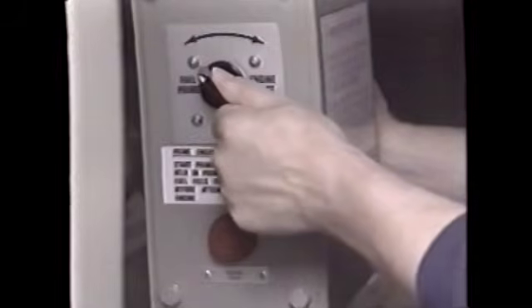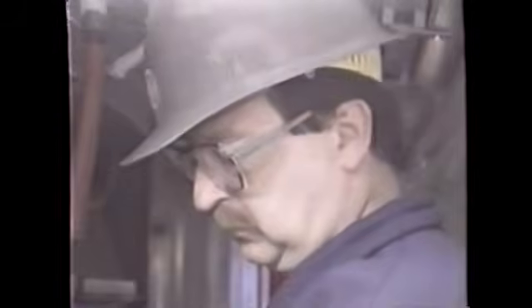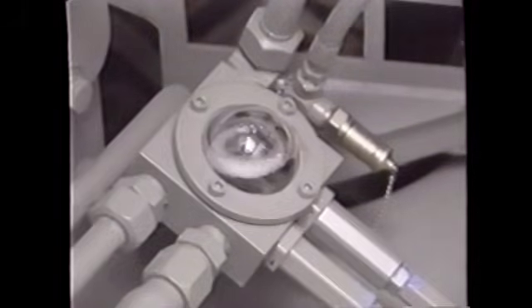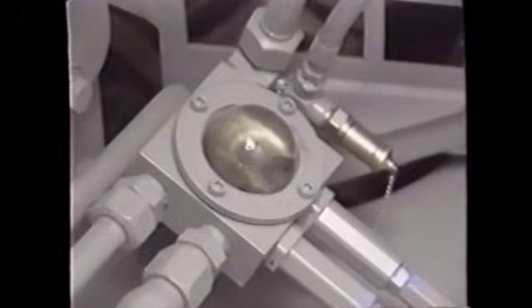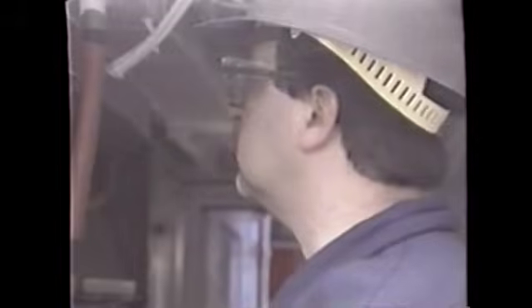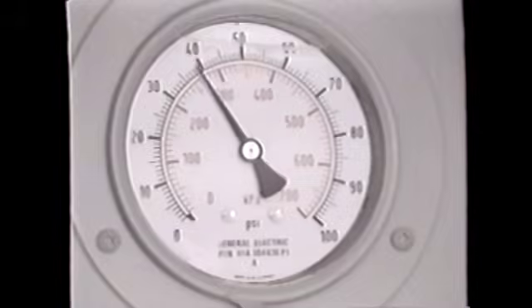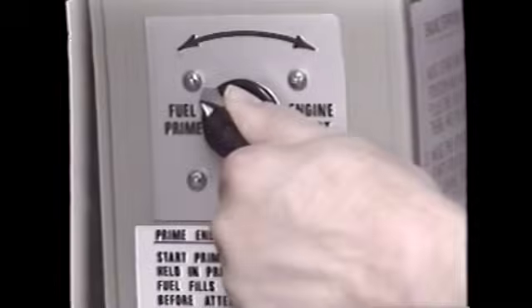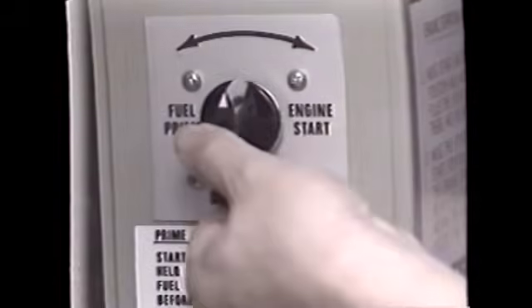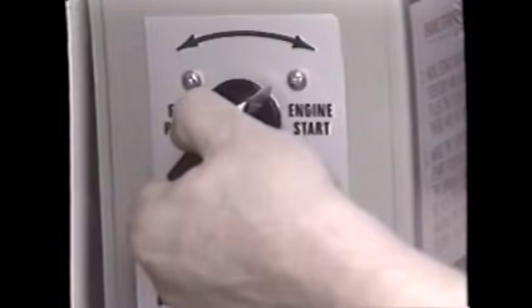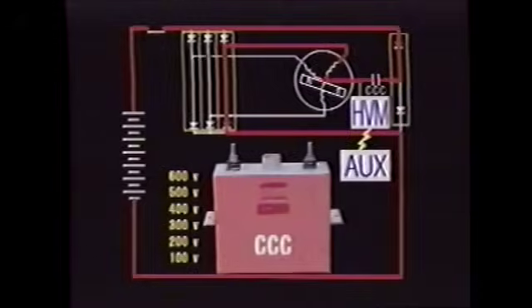Turn the engine start switch to prime. Check the sight glass and hold the switch until the flow of fuel oil is free of air bubbles. When the fuel oil pressure reaches approximately 40 psi, turn and hold the engine start switch to the start position. It takes a few seconds for the computer to complete its circuit checks and preparation.